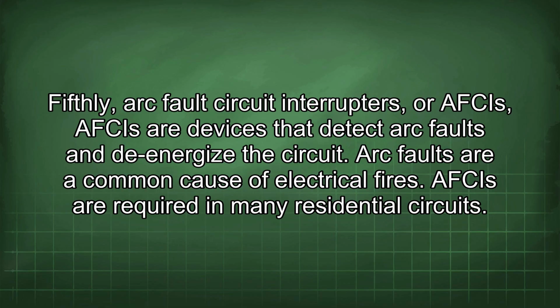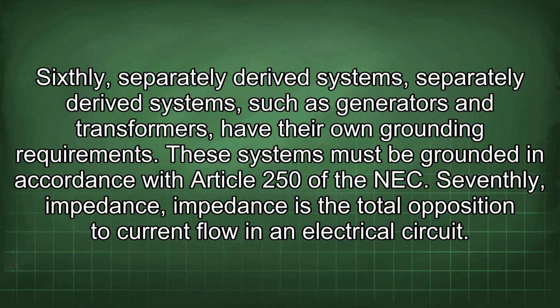AFCIs are devices that detect arc faults and de-energize the circuit. Arc faults are a common cause of electrical fires. AFCIs are required in many residential circuits. Sixthly, separately derived systems. Separately derived systems, such as generators and transformers, have their own grounding requirements.